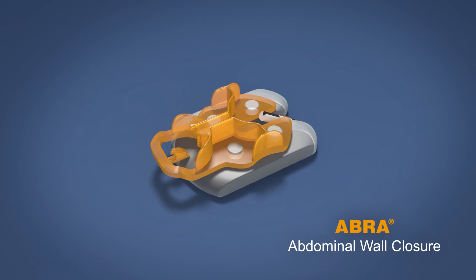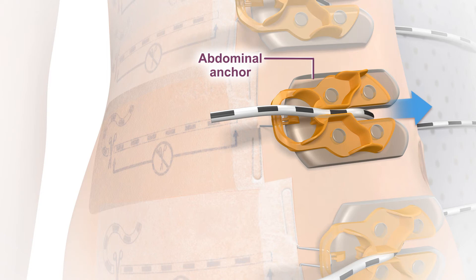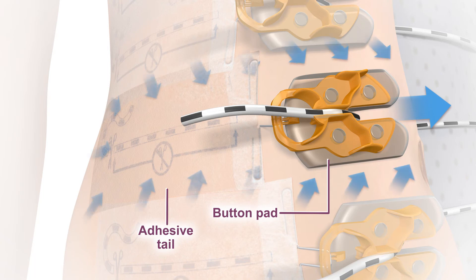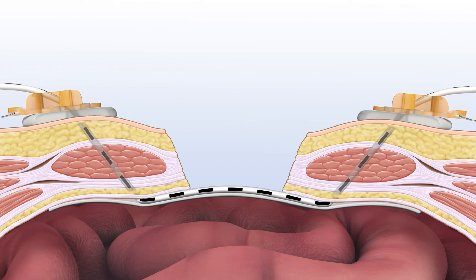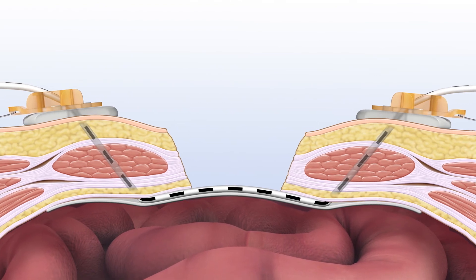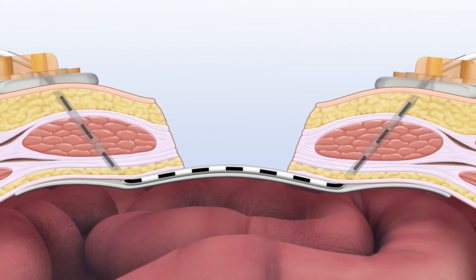ABRA abdominal is specifically designed for abdominal wall wounds. The system applies appositional forces on the retracted abdominal wall by placing each layer of the abdominal wall under therapeutic force. The button anchor secures the elastomer and allows easy tension adjustments. The button pad and adhesive button tail distribute closure forces over a large area of healthy skin, ensuring the elastomer doesn't pull on the skin. Medial traction is applied lateral to the fascial wound edge, leaving the margin undisturbed and available for primary suture closure once the wound has been approximated. A perforated silicone sheet protects the viscera while preventing adhesions from forming.